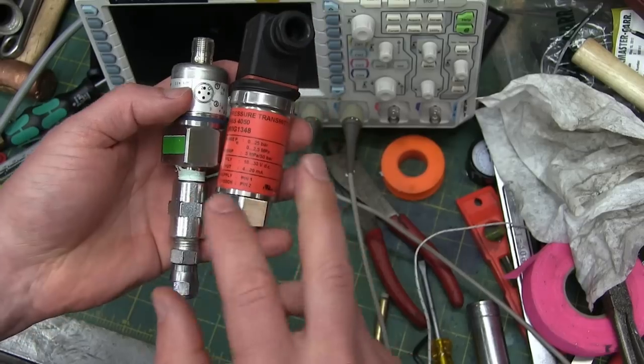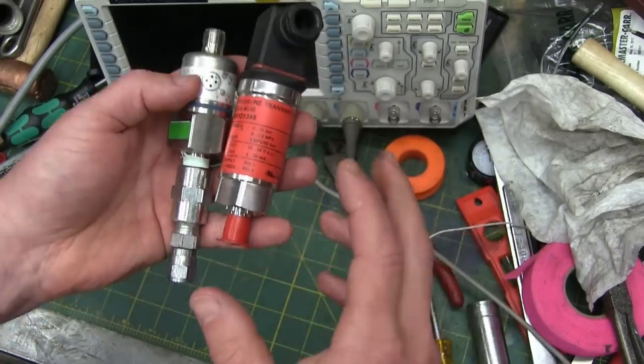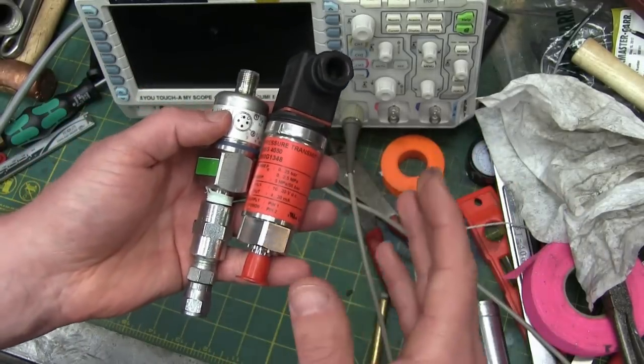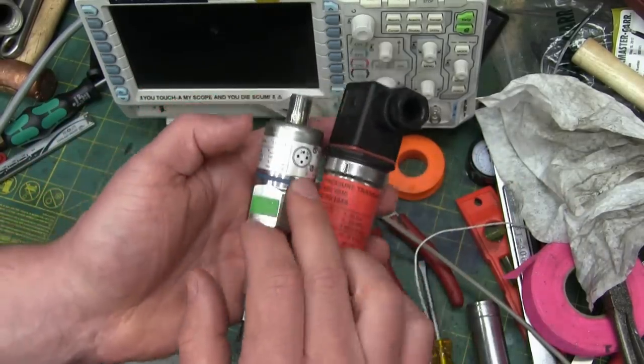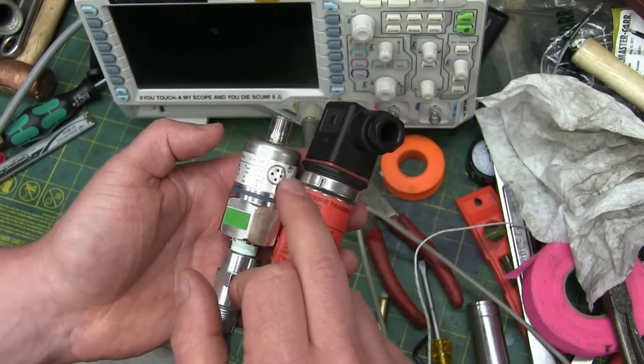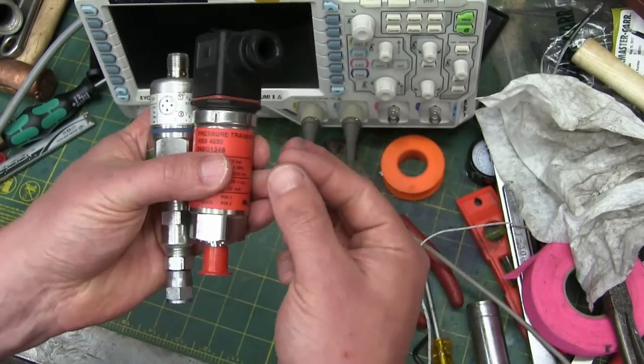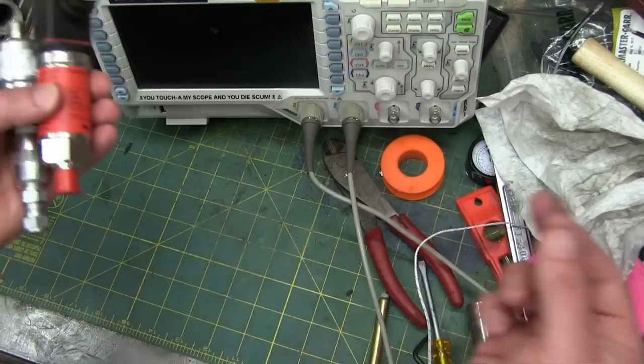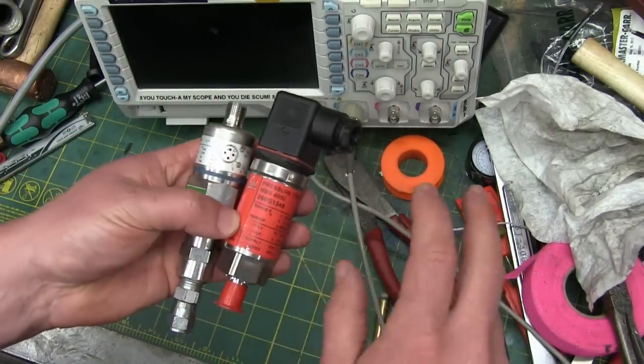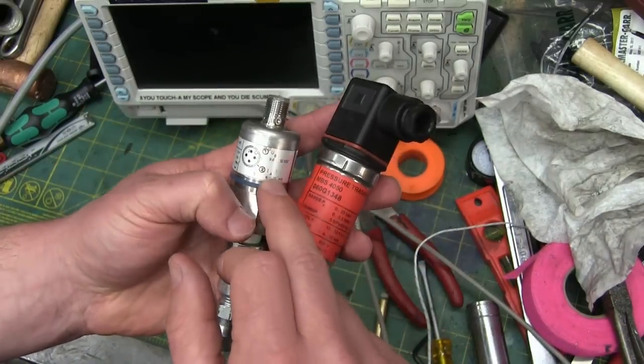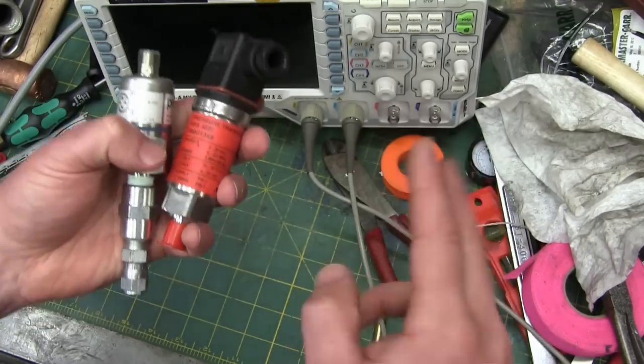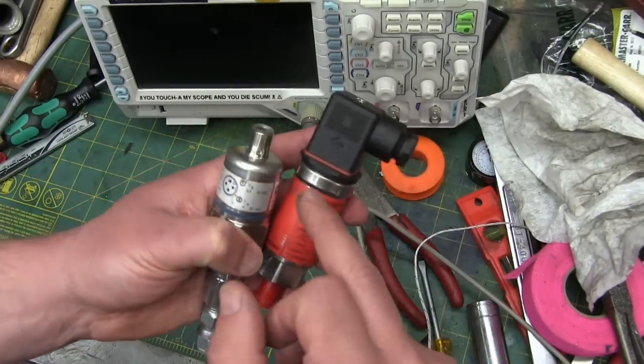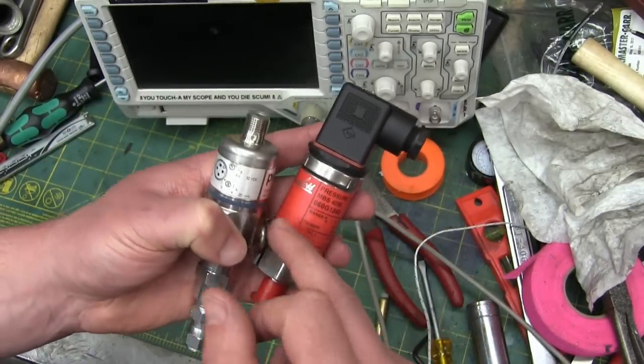But the difference between analog voltage out, the 0.5 volts to 5 volts, is that these are less susceptible to noise and also less susceptible for longer runs of instrumentation cable, less susceptible to voltage drop. So these are quite a bit more robust, but there's a little bit of fancy two-stepping we got to do in order to use that for the Arduino.